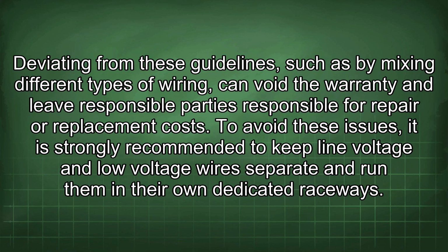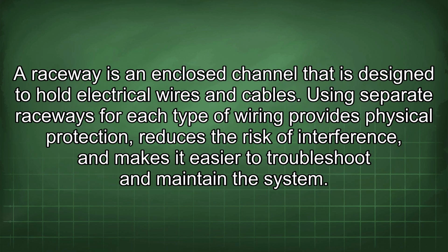To avoid these issues, it is strongly recommended to keep line voltage and low voltage wires separate and run them in their own dedicated raceways. A raceway is an enclosed channel that is designed to hold electrical wires and cables. Using separate raceways for each type of wiring provides physical protection, reduces the risk of interference, and makes it easier to troubleshoot and maintain the system.